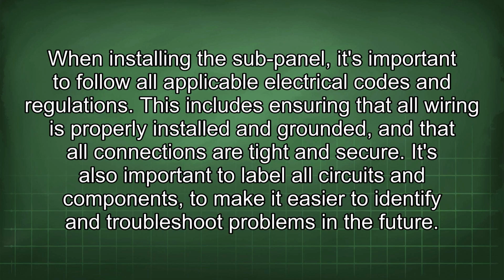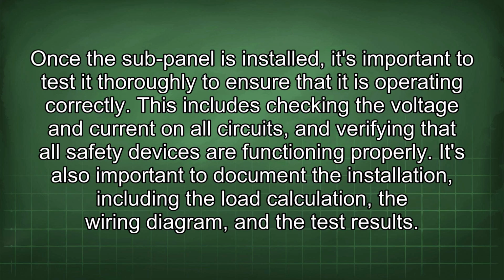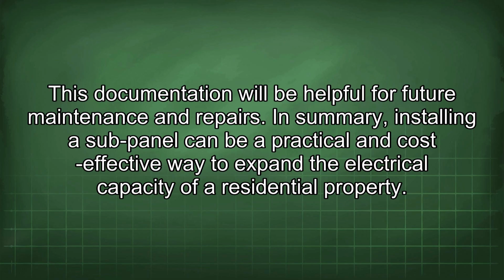When installing the sub-panel, it's important to follow all applicable electrical codes and regulations. This includes ensuring that all wiring is properly installed and grounded, and that all connections are tight and secure. It's also important to label all circuits and components to make it easier to identify and troubleshoot problems in the future. Once the sub-panel is installed, it's important to test it thoroughly to ensure that it is operating correctly. This includes checking the voltage and current on all circuits, and verifying that all safety devices are functioning properly. It's also important to document the installation, including the load calculation, the wiring diagram, and the test results. This documentation will be helpful for future maintenance and repairs.